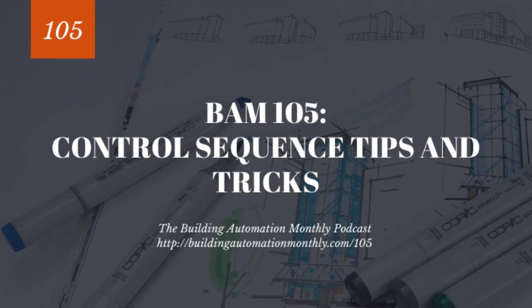And what was happening is that if the primary chillers stage on, then they add more GPM, that GPM overpowers the secondary loop, and that then pulls water from the primary back into the primary, because the primary is now overpowering the secondary, which now the secondary will start to increase its flow to compensate. It starts pulling more GPM. And this is really something you got to visualize. I'm like visualizing it in my head. I'm like, how are folks going to follow this on audio? Anyways, the key point of all of this is that with the decoupled loop, the loop that has the most flow is going to pull water through the decoupler. And what was happening is that no matter what we did, the secondary loop was not getting enough water. And it was just starving for water.